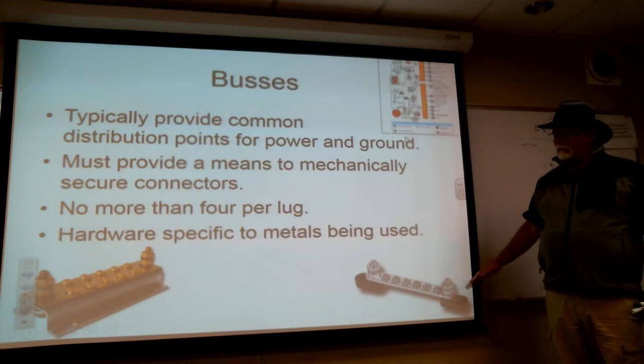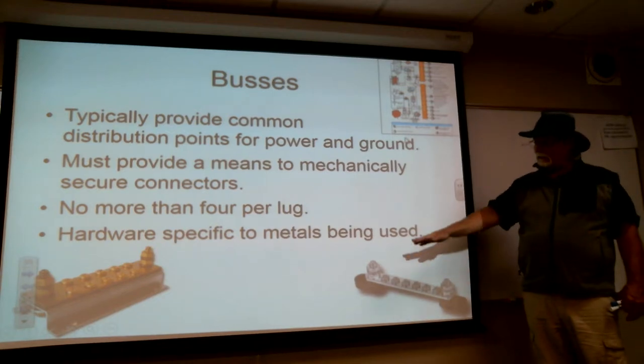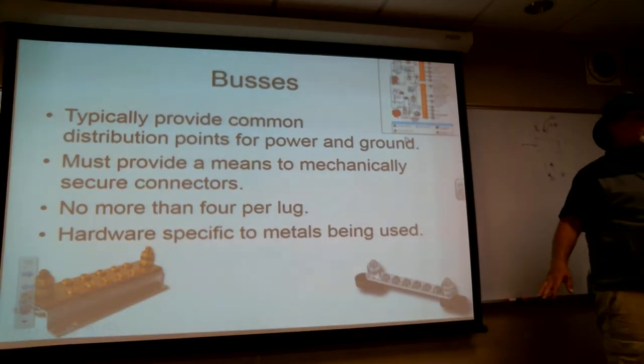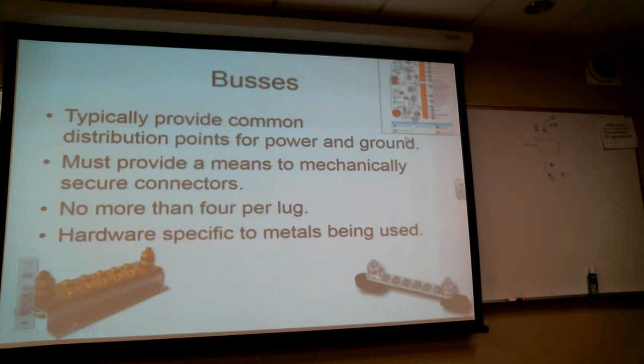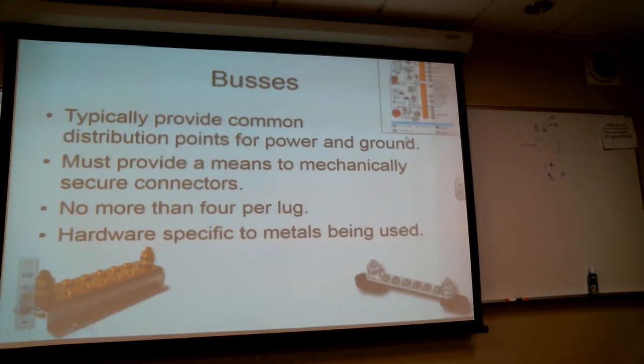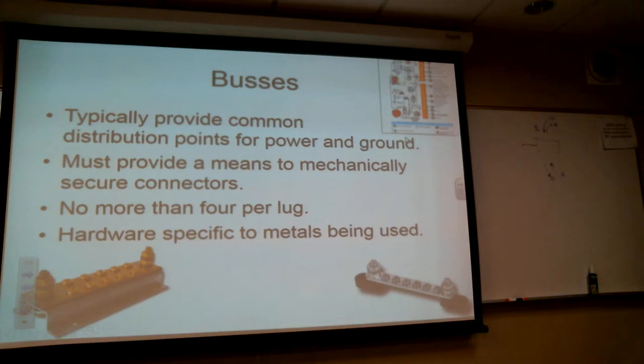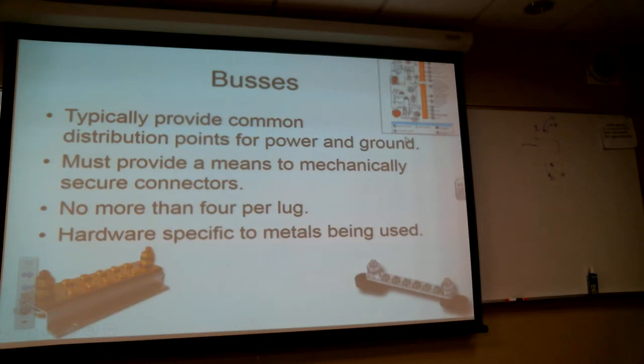You sometimes see this done in aviation by taking a whole row of circuit breakers, and on the hot side you take a copper strip, drill nicely spaced holes, and just screw that copper strip to the distribution side of the circuit breakers — and that becomes your bus.